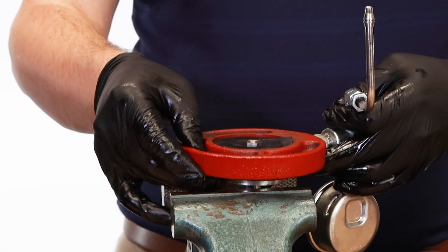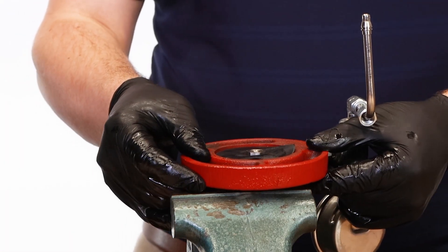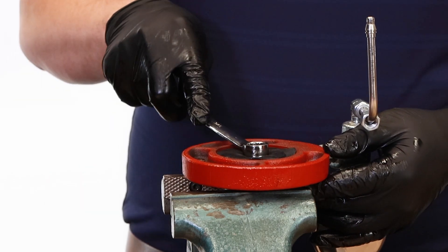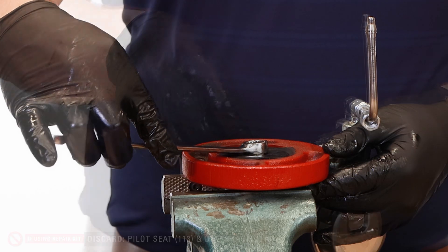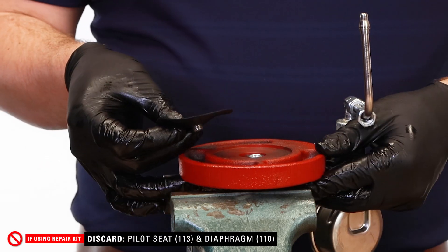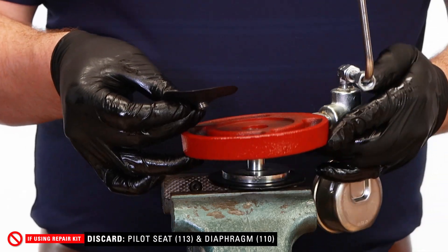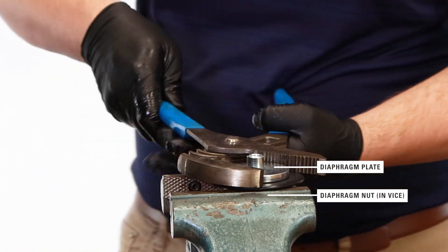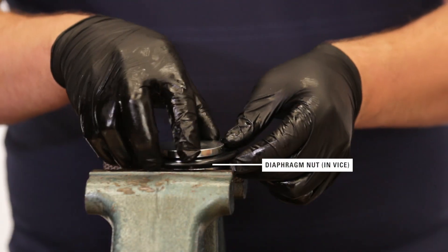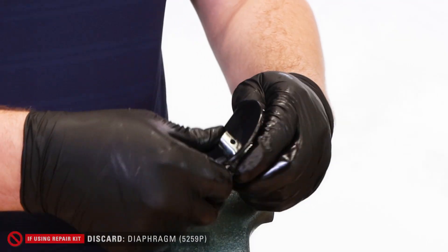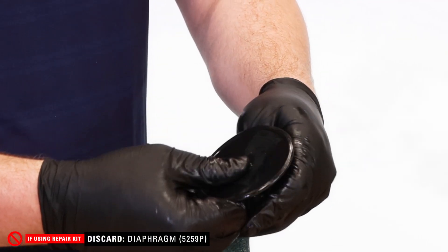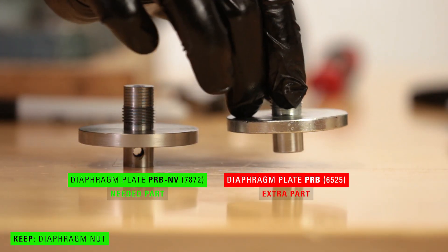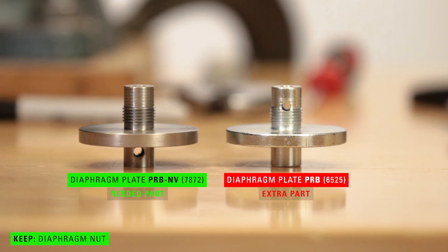Place the pilot housing upside down in the vise on the diaphragm plate. Use a wrench to remove the pilot seat. Inspect the diaphragm and replace it if necessary. Use channel locks to remove the diaphragm nut from the diaphragm plate. Remove and inspect the diaphragm and replace it if necessary. Keep the diaphragm nut, but set the diaphragm plate aside. It will be an extra piece.